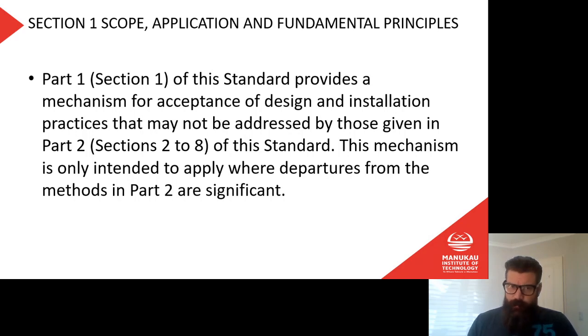So again, just so we really get that into our heads, part 2 tells us all of the stuff that we need to do. Sometimes we might need to do something that's not covered in part 2, so we refer back to part 1 for the generic rules. We come up with our own design, prove that it is safe, and then we can use that. Again, we don't generally do that. The vast majority of what we do would just be covered by part 2. And as it says there, for part 1, this mechanism is only intended to apply where departures from the methods in part 2 are significant.